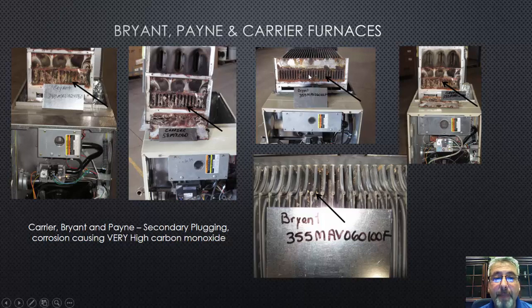This is what's happening. They plug up. So here's what I want to share with you. If you just inspect the heat exchanger with your visual tools or your sophisticated camera system, that's not enough. You must connect your combustion analyzer to the exhaust and check that carbon monoxide. Notice down here, secondary plugging is what I wrote about. So plugging here, plugging here, plugging here, severe plugging here. Now realize I took these furnaces apart, dismantled them. You're not going to see this by taking the door off the furnace. You have to literally break these things down to get to this point. So you won't see this.